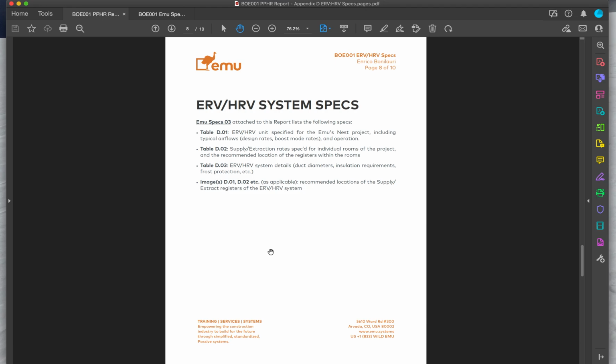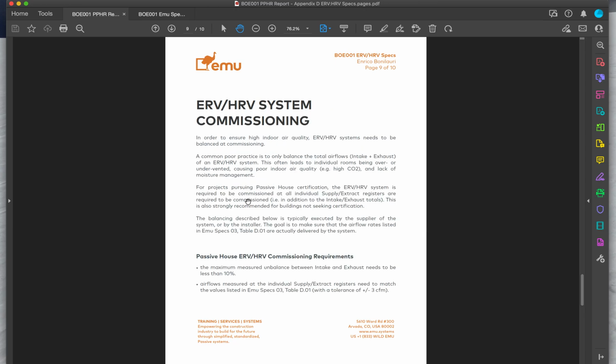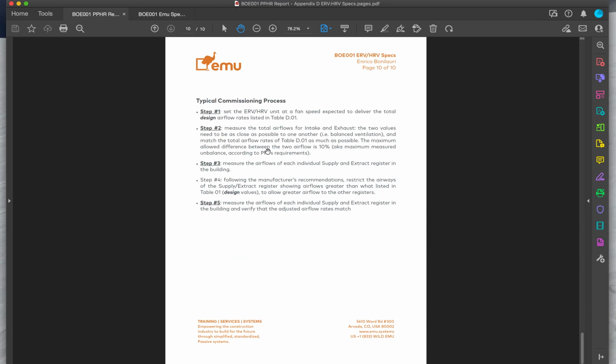The specs, this is something that we're going to see in the next document, so I'm going to skip over that. Some indication about commissioning. And even if you're a homeowner or a builder, this is something that you want to know. Your HVAC contractor may be the best at installing and commissioning ERVs and HRVs, but it could be as well a first timer. There's nothing wrong with that. You just need to know that this kind of system needs to be commissioned at every individual interior register. There is no such thing as an ERV or HRV that self-commissions or self-balances. That's a pretty big misunderstanding of the language.